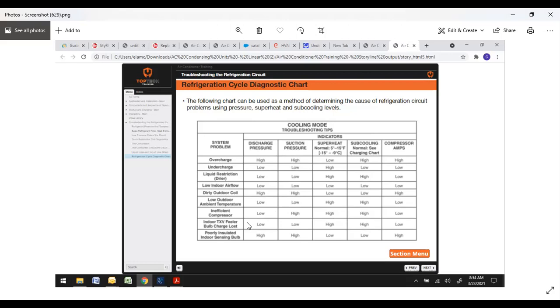And then we get into the TXVs. If your indoor TXV bulb lost its charge, you could have low discharge pressure, low suction, high superheat, high subcooling, and low compressor amps. You could have a poorly insulated bulb or a misaligned bulb. So you could have a high discharge pressure, high suction, low superheat, low subcooling, and high compressor amps. A lot of times what you'll see when you walk up to a bad TXV is your suction pressure won't be bottomed out, but it'll hang out just below. It'll hang at about 15, 20 degrees, which is going to freeze it up.